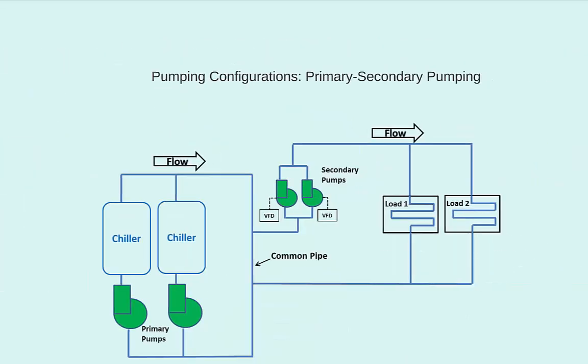It looks like this. You have two separate piping loops, which are connected by a common pipe. This common pipe is often called the decoupling line or the neutral bridge. Flow can go either direction through this common pipe, or not flow through it at all. Let's walk through a couple examples.